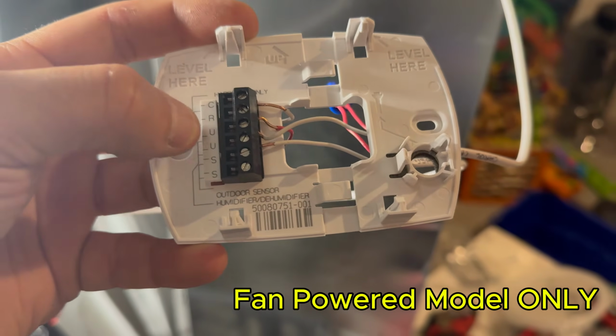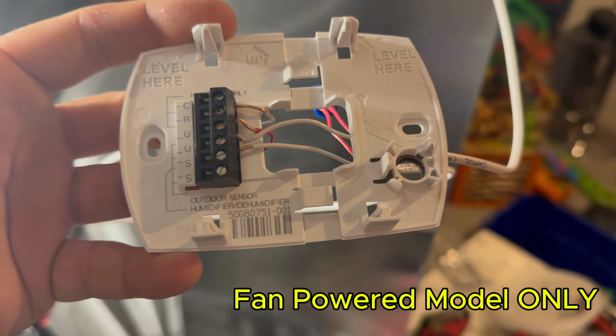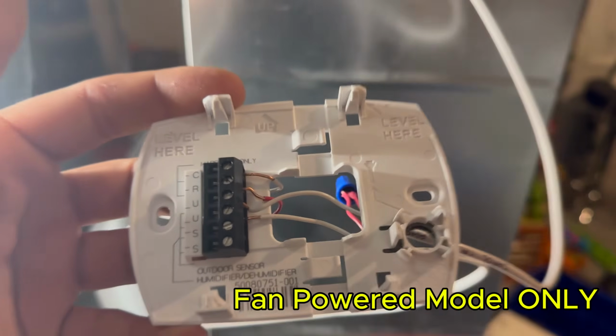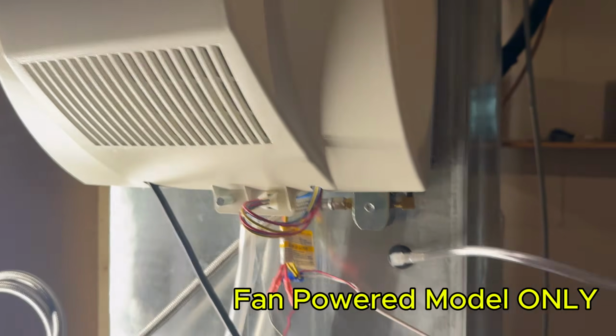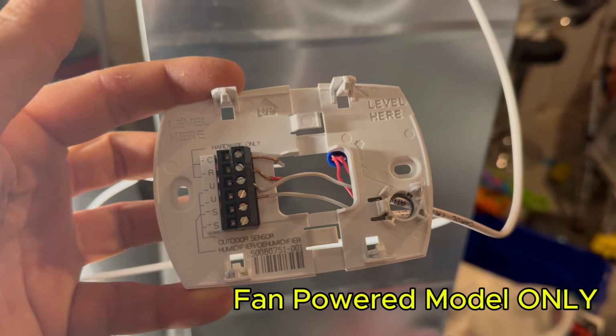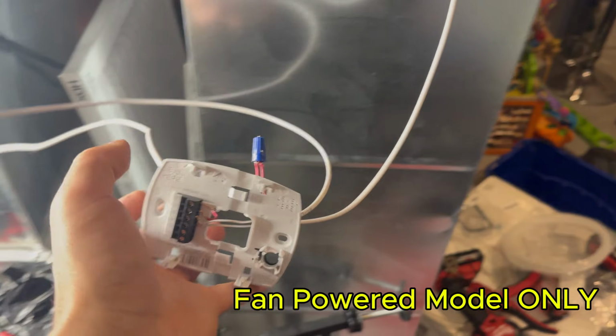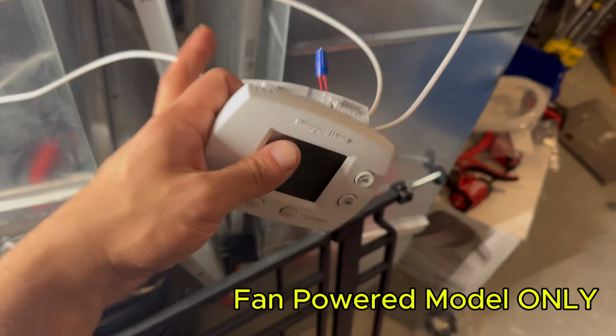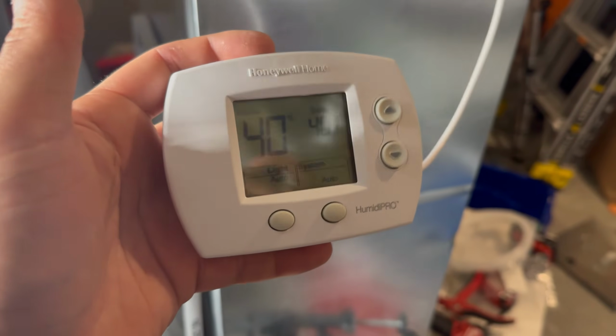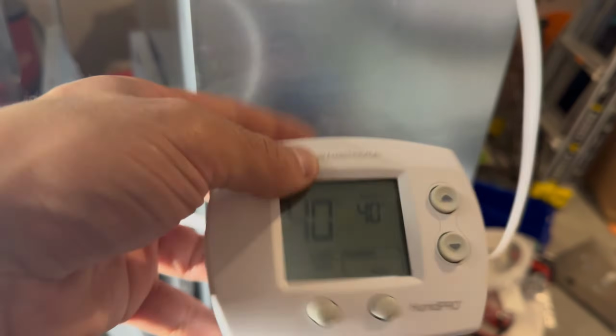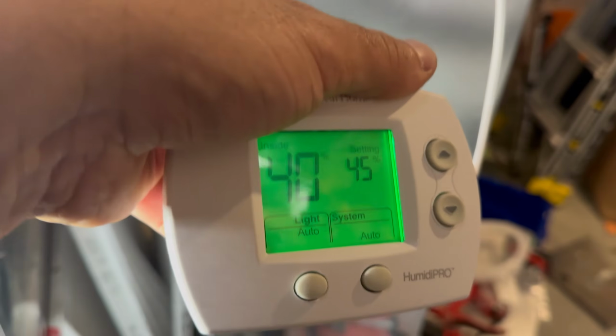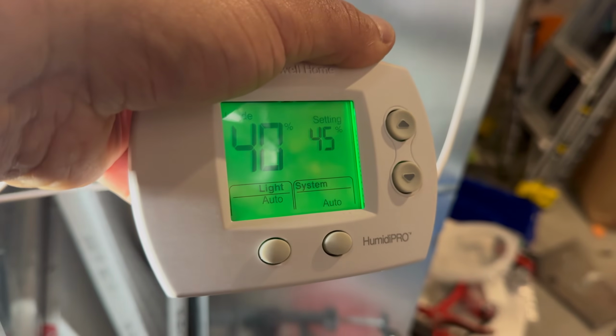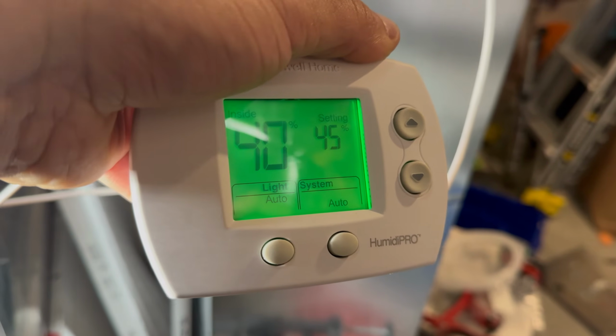U. So there's a U and a U. You're going to connect those 2 U's, again, one coming from the pressure switch and one coming from the humidifier. And that's all there is to it. And now, once this is mounted and powered up, which I'll show you in a second, let's do that now. Connect this here. There you go. Once it's plugged in, you'll see now, if I increase the humidity, you should hear a click. And there it is. And now my humidifier is running.